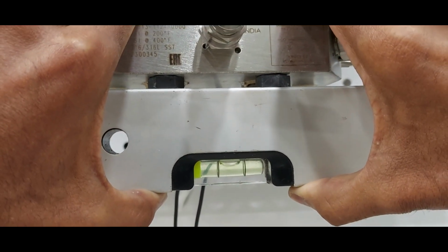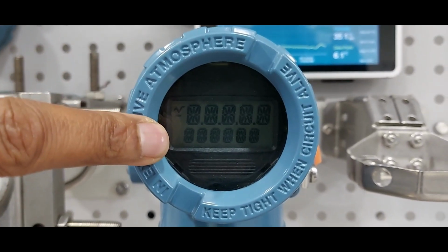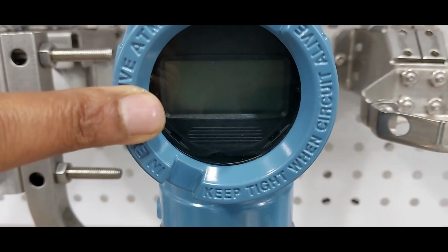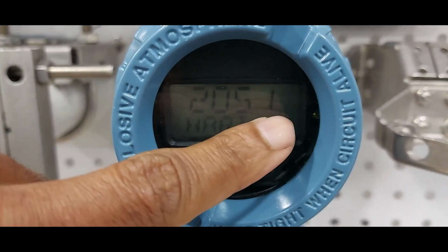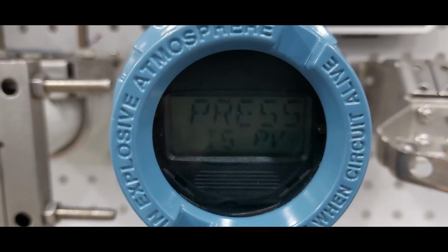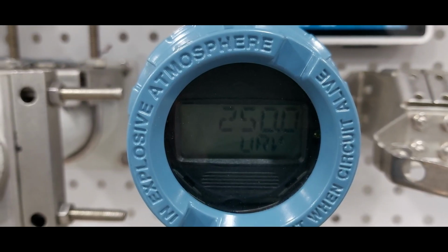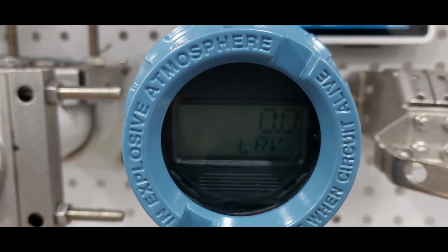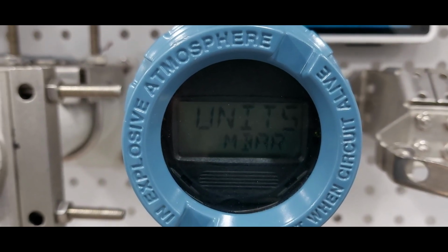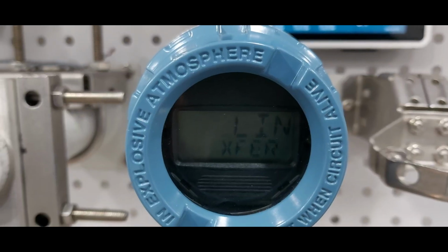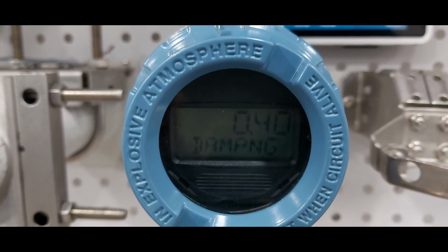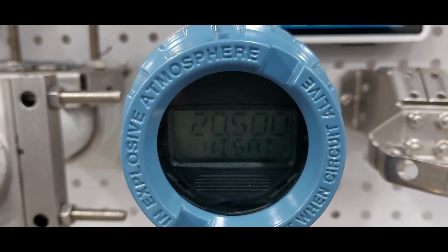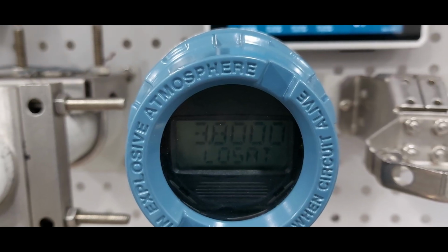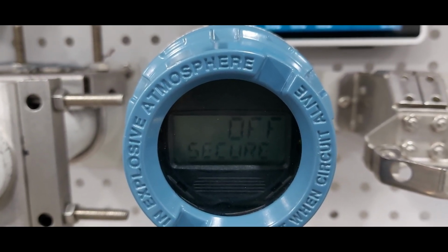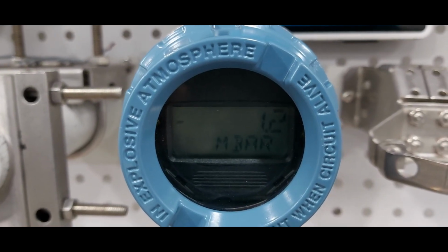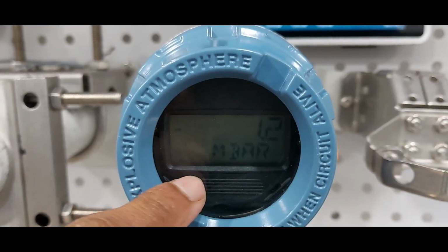Check the transmitter local display condition. Now the transmitter is powered on. 3051 model. LRV, URV, unit is millibar. Linear function, damping, alarm level, saturation level, low saturation level, security is off condition. Now the display is showing 1.2 millibar.